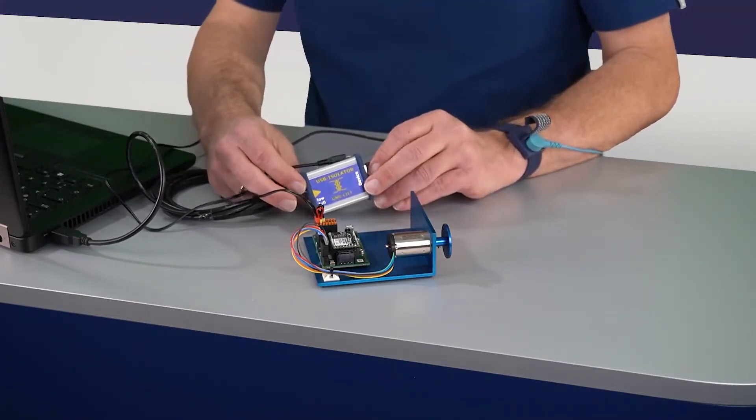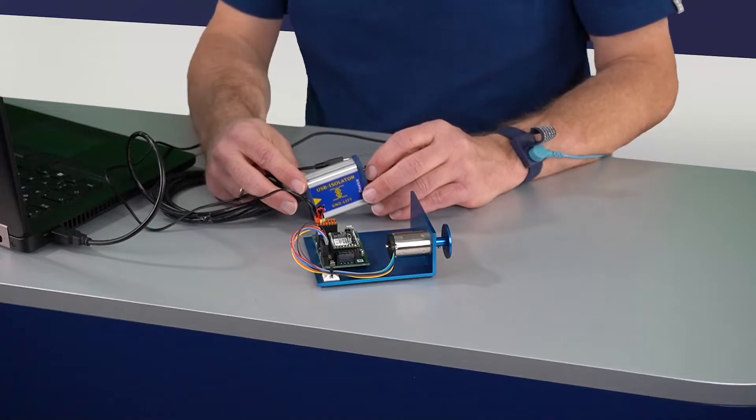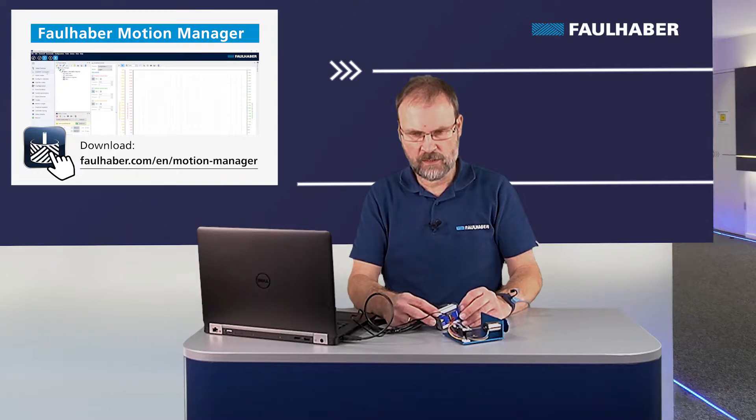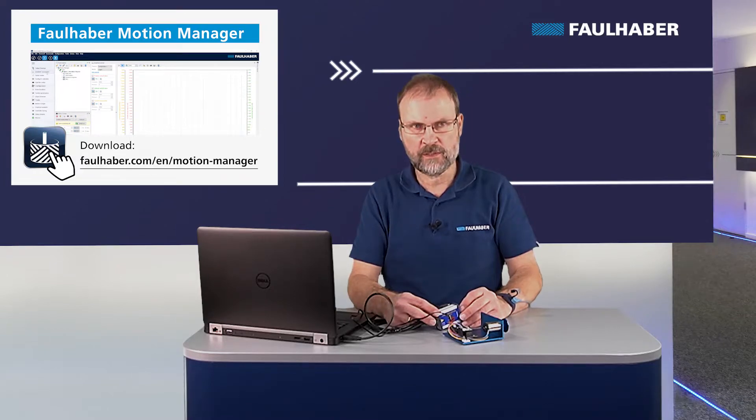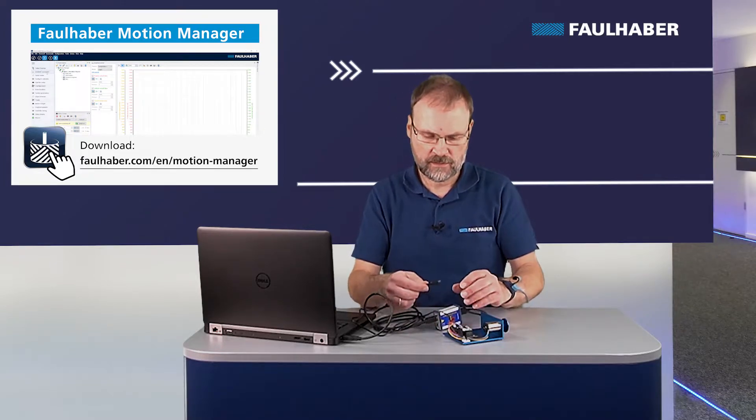Out of habit I'm using a USB isolator because when using electric drives you could have a ground shift, and then you're at risk of damaging the USB port of your PC.